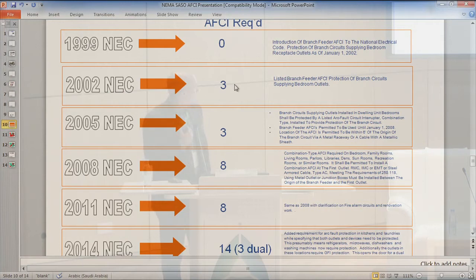And at this point now, we have a requirement for arc fault in the laundry rooms and kitchens, in which case we have a circuit breaker which is coming out as we speak, which includes ground fault and arc fault protection in the same device. And that gives the homeowner several advantages and some added level of safety that they didn't have before. So if you look at this, you can see that we progressively introduced it. Admittedly, there were some growing pains with nuisance tripping and so forth, but now we all have commercially viable products, and everybody's enjoying the benefits of that safety.